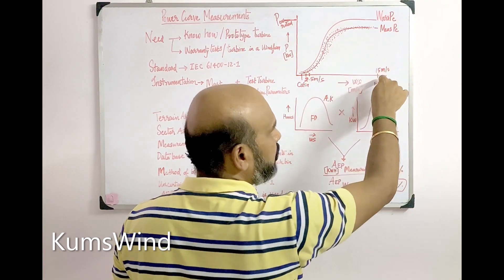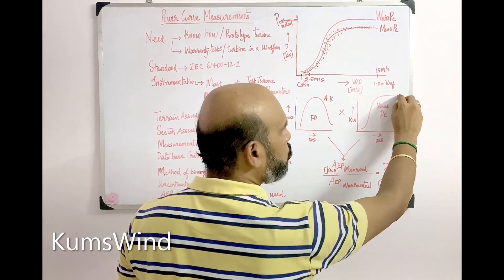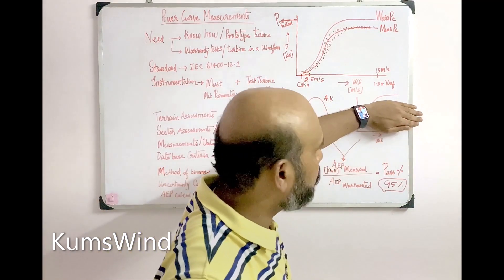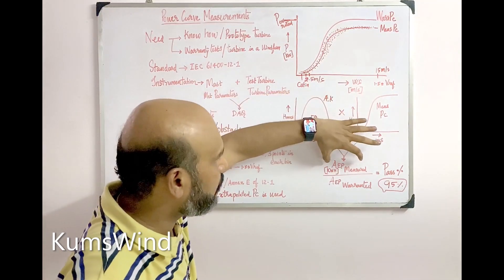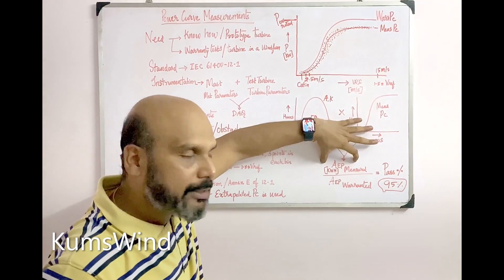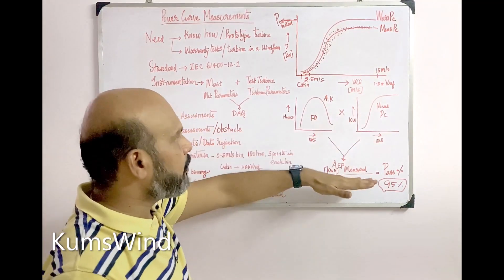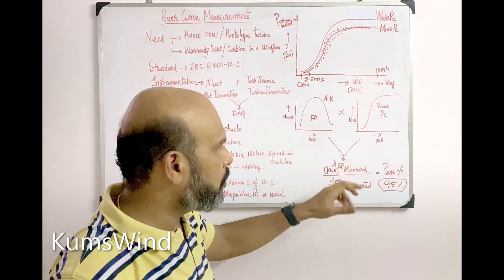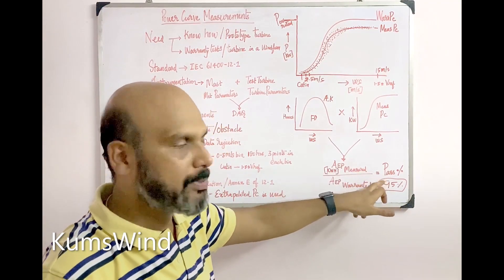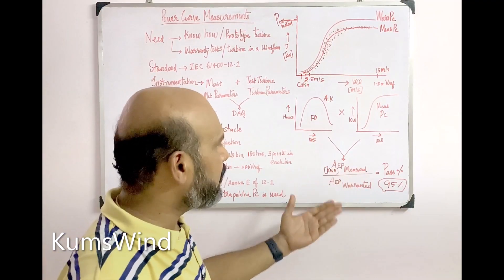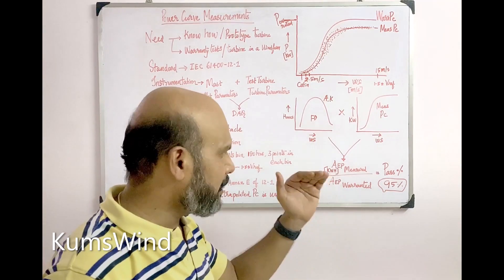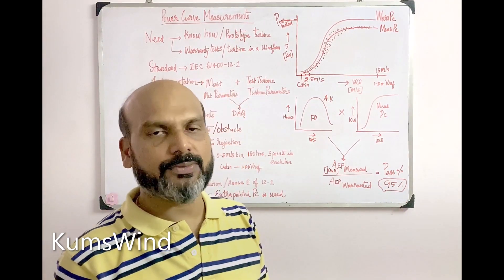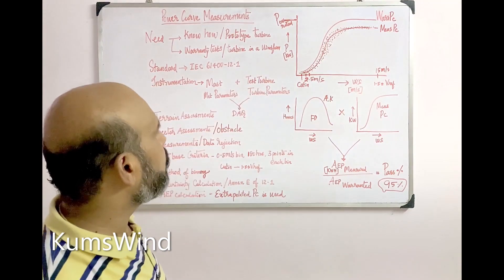After extrapolating the measured power curve to the cut-out wind speed, you use the frequency distribution to calculate the measured AEP. Similarly, substituting the warranty power curve gives the warranty AEP. Taking the ratio of measured AEP to warranty AEP gives the pass percentage or performance percentage. In the industry today, 95 percent is the benchmark — most turbine OEMs are expected to perform above 95 percent as required by wind farm owners.